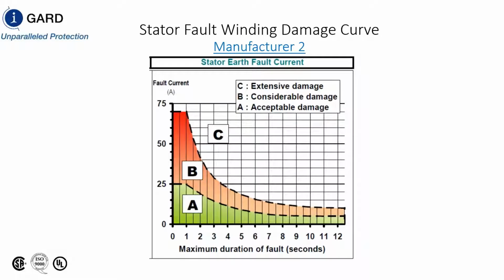Second manufacturer has a different type of curve, but it's a stator earth fault current. So you can see that for A, you have acceptable damage, and it's limited to 25 amps for 1 second and decays. Considerable damage if it's in this B curve, and that's up to just under 75 amps of current. So you can see that generators considerably cannot tolerate a lot of current during internal stator fault windings. And then you have extensive damage if you exceed the time or current in these particular curves.